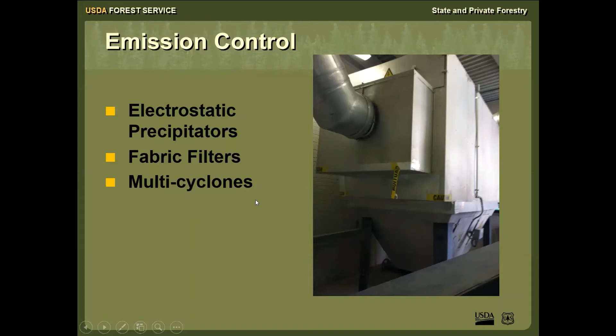The one concern we have about using multi-cyclones is you've got to be careful about how they perform at lower output levels of your system. Usually they're geared to perform the best at high output levels, and to some extent some of their performance curves drop off as the system's output drops off.